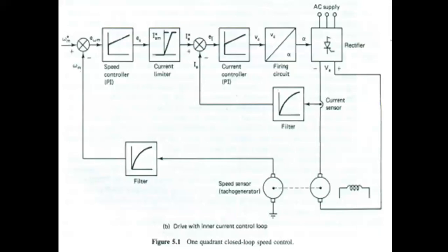So to obtain a fast transient response, much higher transient currents are allowed by selecting a large size rectifier. Now, current regulation is needed only for abnormal values of current. In such cases, due to its simplicity, we take the current limit control, as explained.